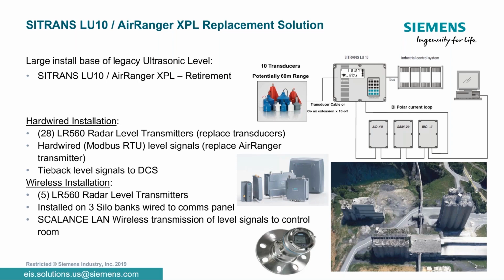So this solution, we replaced the entire system, or retrofitted the old AirRanger with new technology. We have the Siemens LR560 continuous radar level transmitter. We updated the technology, and we also included the hardware to take the signals and communicate all that information back to the customer's DCS.